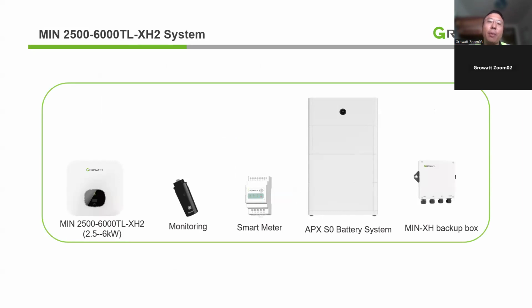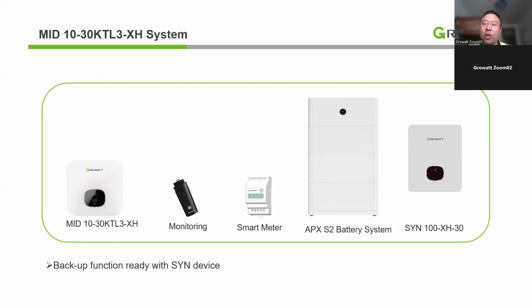I want to emphasize that our battery-ready solution does not have an inbuilt DC isolator and does not have an inbuilt ATS. So if your client wants backup mode or backup functionality, they always have to buy the backup box: single phase uses the MIN-XH backup box, and 3 phase uses the Mid SYN backup box. This is for the larger 3 phase system.